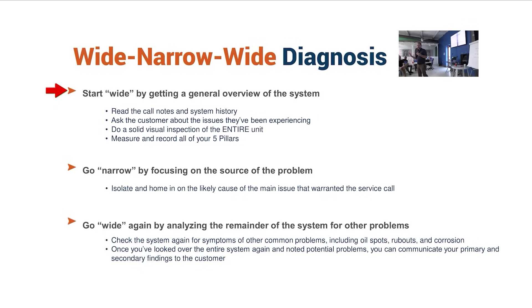When you're talking to the client, you don't want to initially narrow into what's wrong right now. You want to ask questions that give you that bigger picture. How has it been running prior to this? When's the last time you had maintenance done? Have you noticed any other problems in the home? Any humidity issues? You ask those big, wide questions. Don't try to focus on what is wrong right this second — stay big.